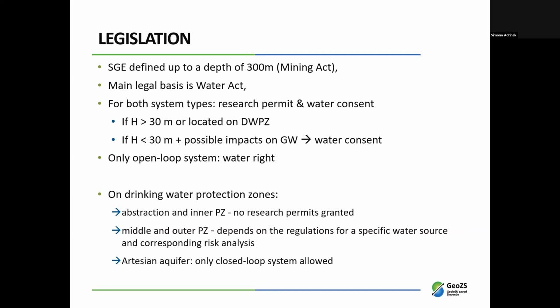For both systems, a research permit and water consent must be obtained if the wells are deeper than 30 meters or are located in the drinking water protection zone. Regardless of the borehole depth, for open loop systems a water right must also be obtained.